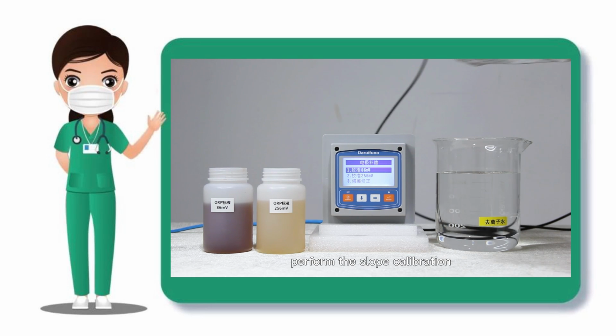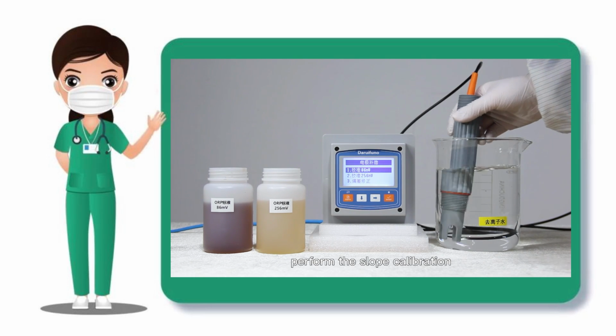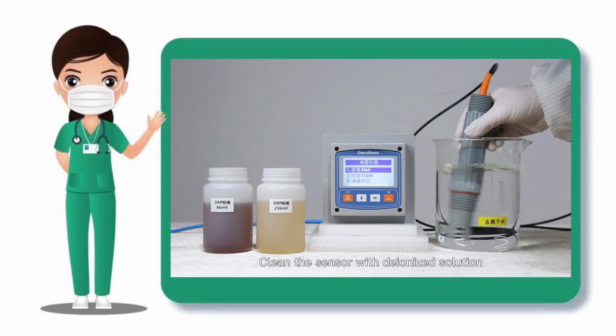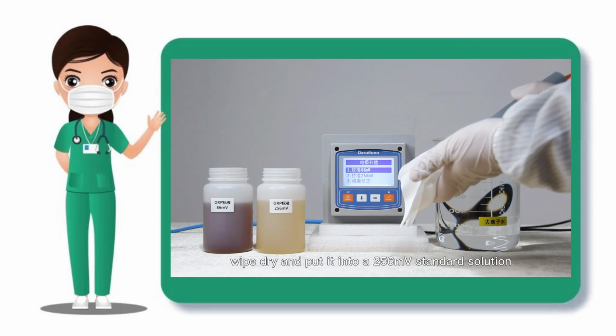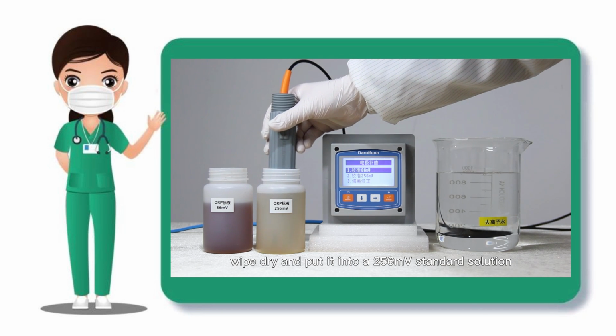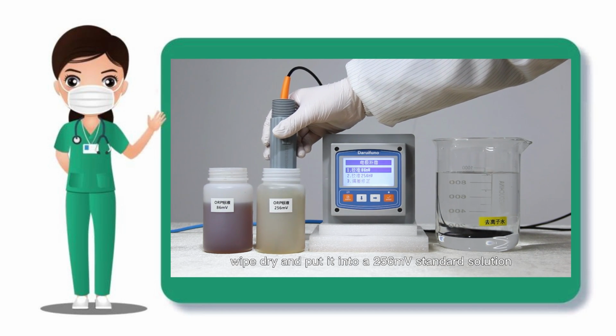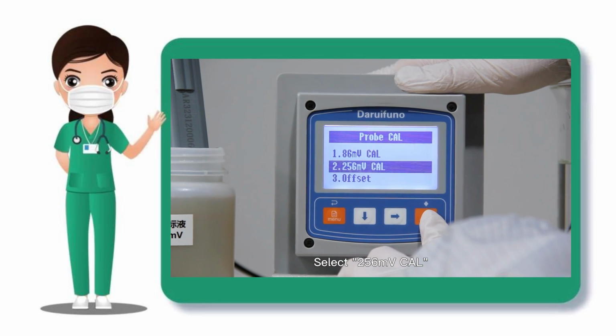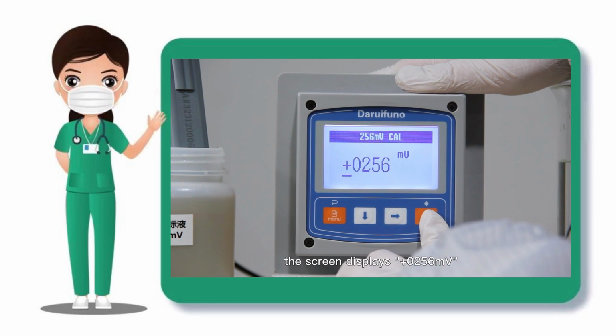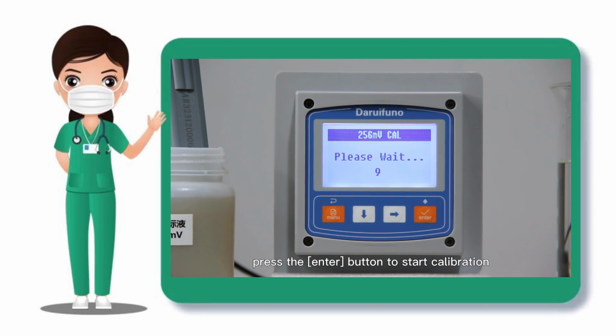Next, perform the slope calibration. Clean the sensor with deionized solution. Wipe dry and put it into the 256 mV standard solution. Select 256 mV cal. The screen displays plus 256 mV. Press the enter button to start calibration.